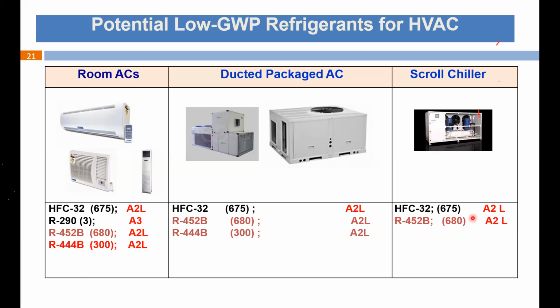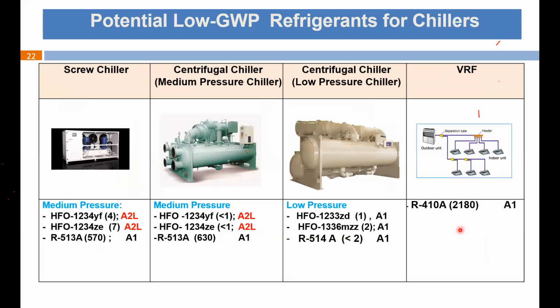For scroll chillers, R32 and R452B are the options. Coming to screw chillers, HFO 1234ze, as I told you earlier, is already launched by some manufacturers. It is being used in some developed country markets. At the same time, 1234yf is also being used. And R513A refrigerant based screw chillers have also been launched by some manufacturers. For medium pressure, the options are more or less the same. For low pressure centrifugal chillers, HFO 1233zd, 1336mzz and R514A are the options.